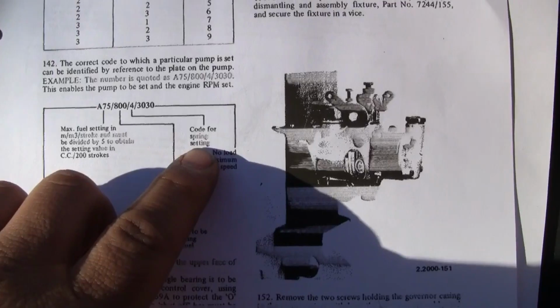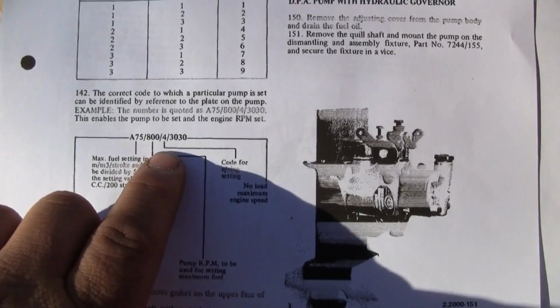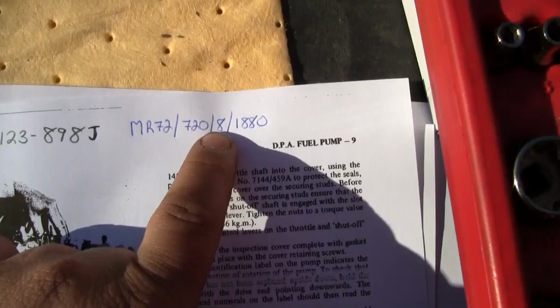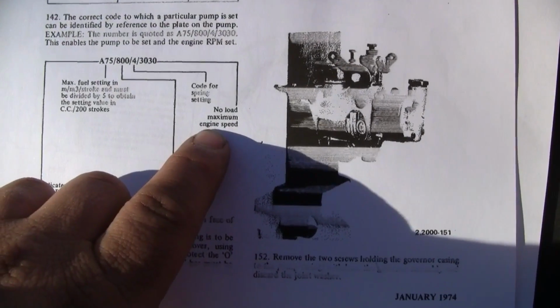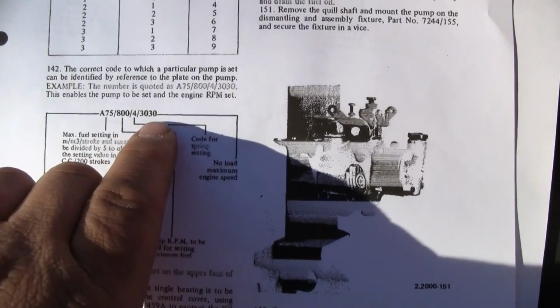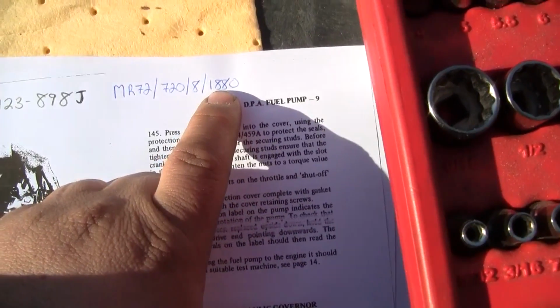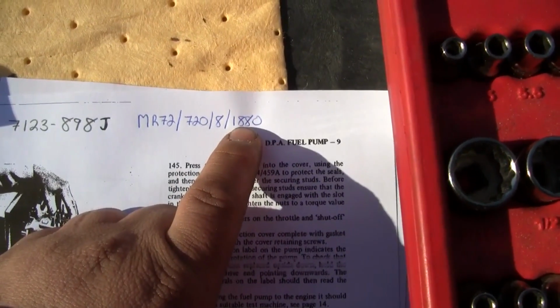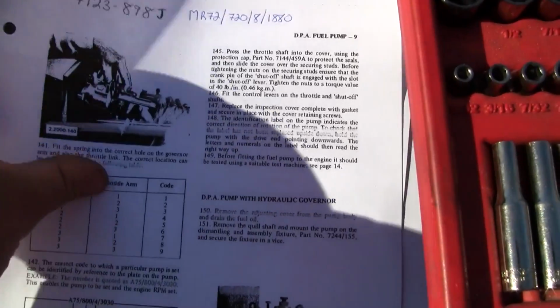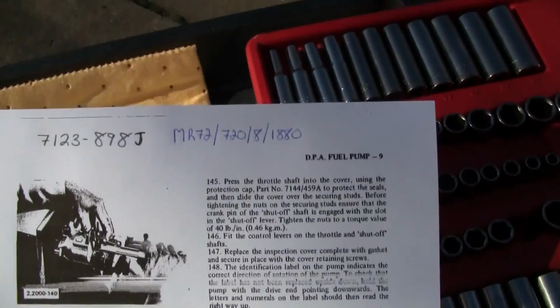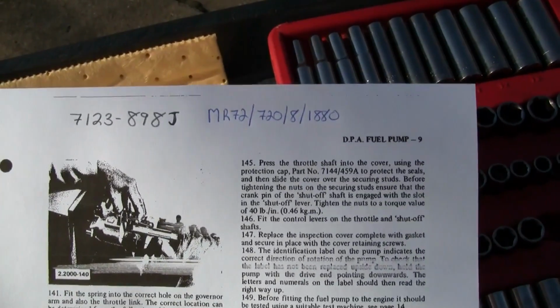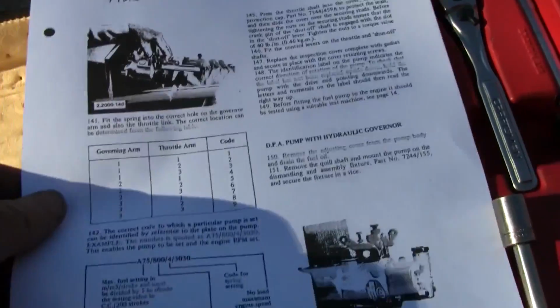The important one for me is the code for the spring setting - that's the governor spring. The example is number 4, I am a number 8. The last relevant number is the no-load maximum engine speed - in this case 3030, but my pump is an 1880, which comes out to 62.6 hertz. That's a bit higher than I'd like, but we'll set it to 62.6 when we do our initial load testing.